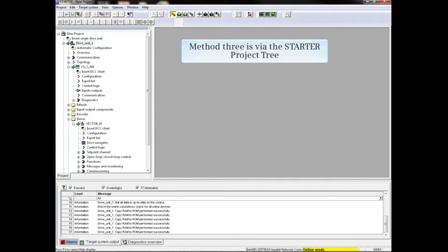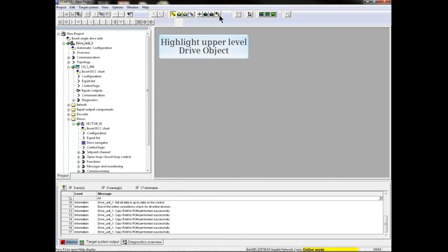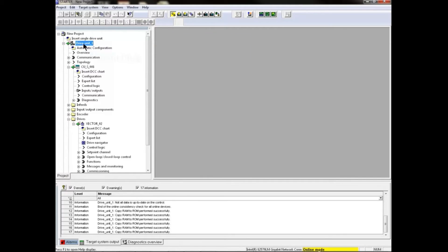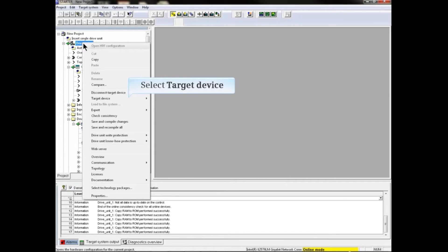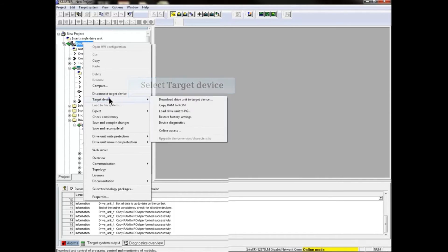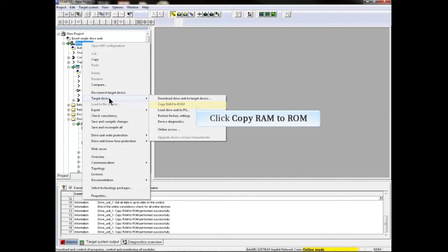Method three is via the Starter project tree. As with the other methods, we start by highlighting the upper level drive object. We then right-click on the upper level drive object to activate the project tree sub-menus. In the drop-down menu, select the Target Device menu item, then click the Copy RAM to ROM menu item from the second drop-down menu.